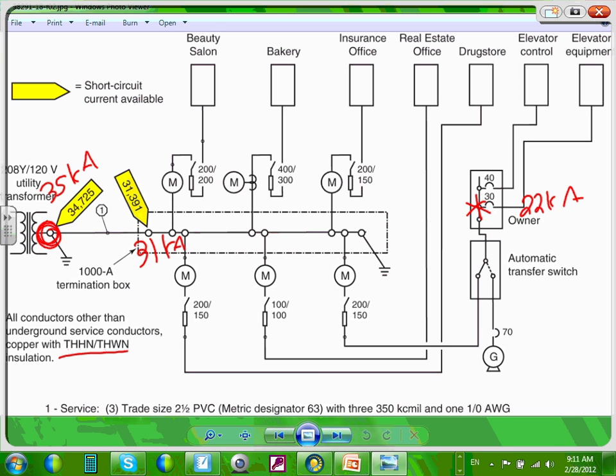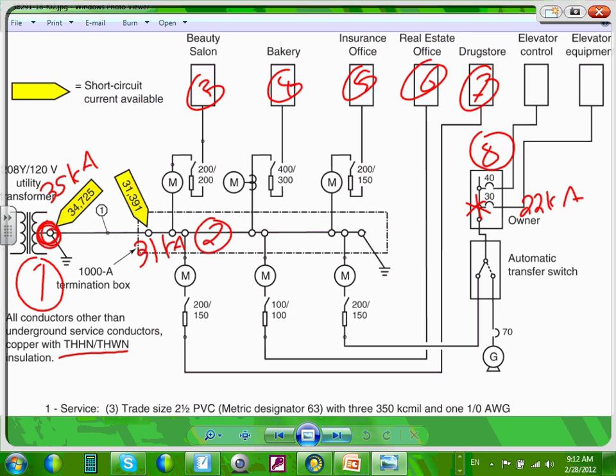So when we do short circuit calculation, guys, here's how many calculations you're going to have. You're going to have one calculation here, one in this switchgear, two, and one calculation for every panel: 2, 3, 4, 5, 6, 7. I have 8 here, 8 calculations, meaning I need to calculate the short circuit for 8 panels. And based on these 8 calculations, I can size each panel.